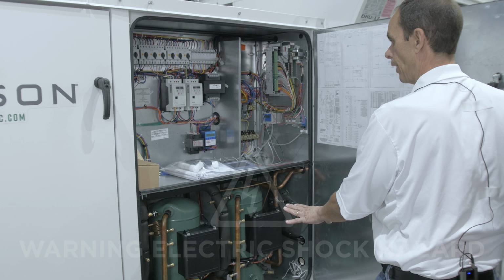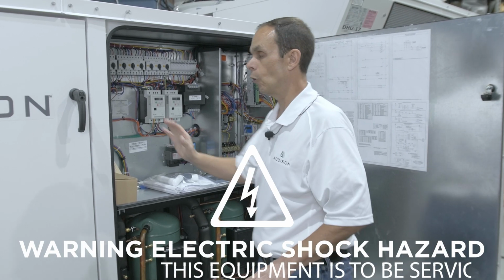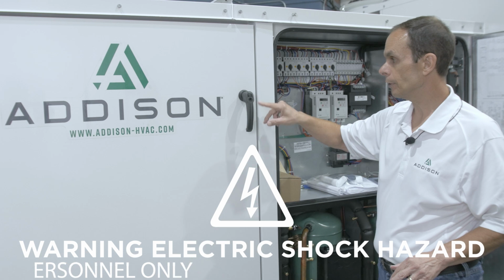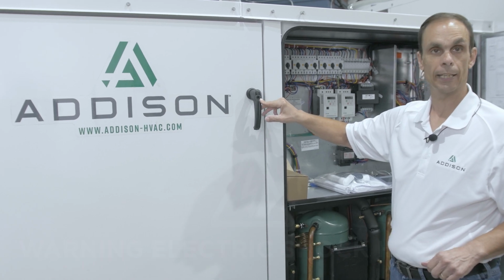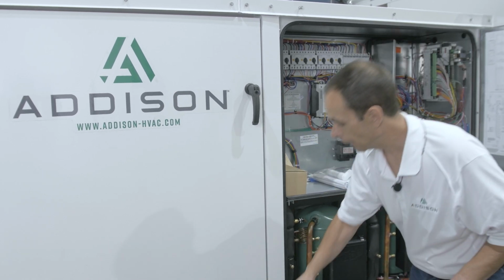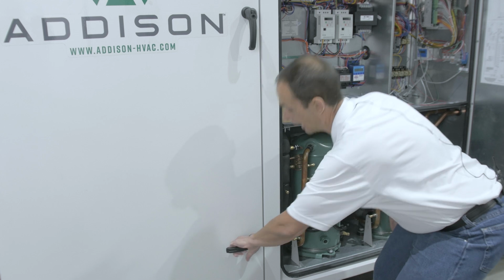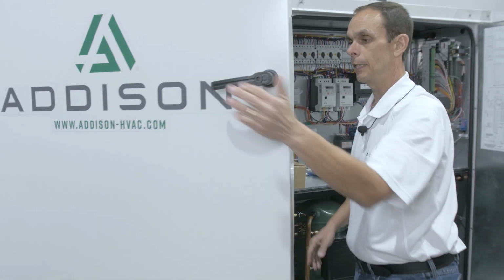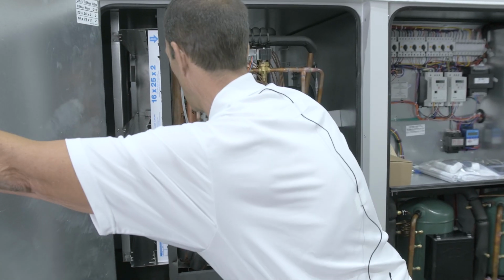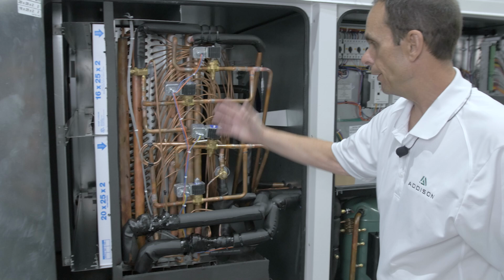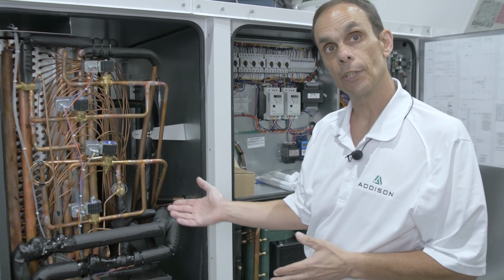controls and compressor section. The door to the left of that, and here I want to point out, is that we have on our handles, the top one is a locking. It's going to take a 5/16 Allen wrench. The bottom one is not a locking handle. Here is going to be access to your outside air filters and your coil section. So let me go a little bit more detail.